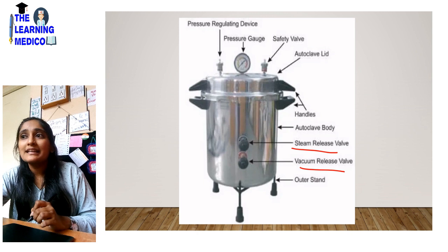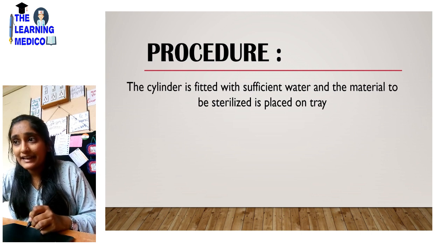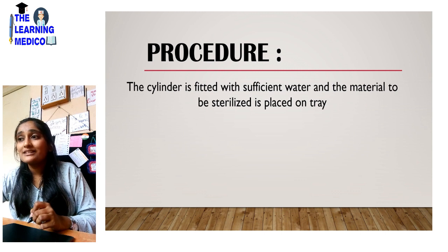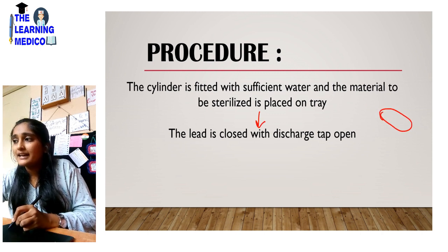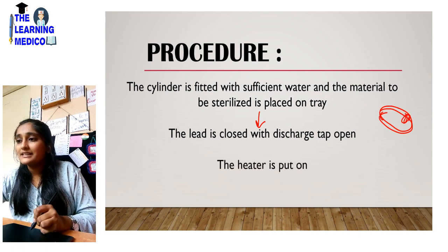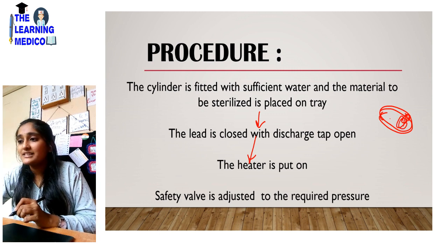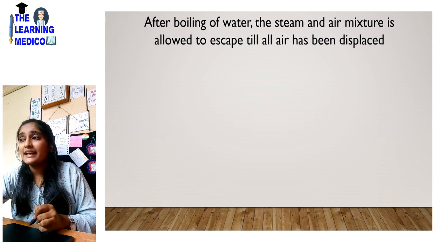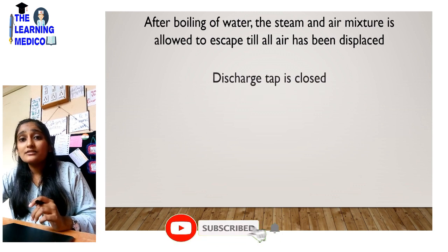Go to your college lab and see it — when you see it, you will understand better. For the procedure: the cylinder is filled with sufficient water and the material to be sterilized is placed on a tray. The lid is closed with the discharge tap open. The heater is turned on and the safety valve is adjusted to the required temperature. After boiling of water, the mixture of steam and air is allowed to escape until all the air has been displaced, and then the discharge tap is closed.